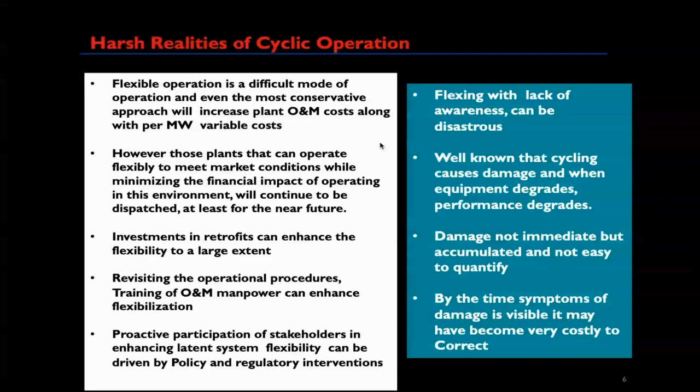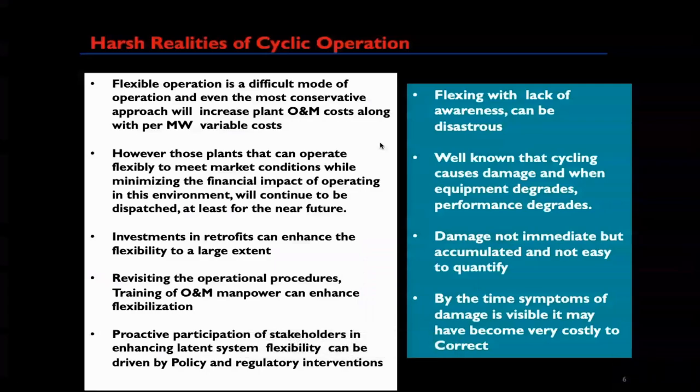Today, when you talk to the operators, they are afraid of many things. Like when you tell them to operate a simple HP bypass, they are fearful. They fear that maybe the unit will trip on drum level and all. But we have seen these things happening in Germany. Last year also, they were training under this IGF program. We had visited the simulators and seen that they operate the HP bypass. And it will take a minimum of 5 to 10 minutes for the boiler to stabilize if you raise or lower the loads to coal.